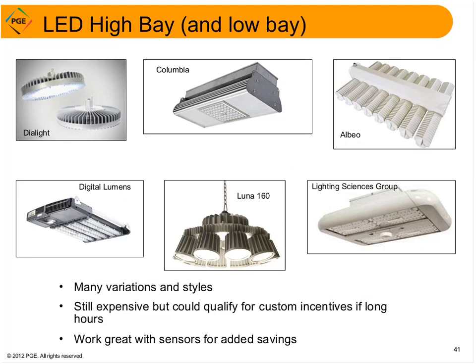This fixture from Digital Lumens has been especially successful for this application because they're replacing usually high-pressure sodium that has to be on 24/7 because it takes so long for the fixtures to come to full brightness when they're turned on. These environments are often 20 degrees below zero. So this LED fixture works great because LEDs like it cold and they don't mind frequent switching.